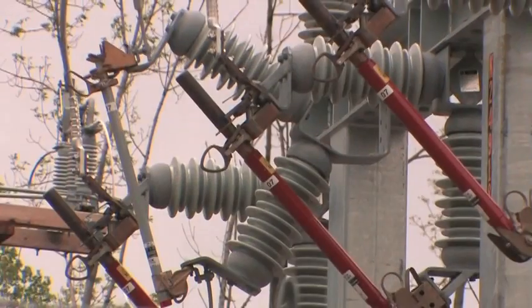The construction and development of the power plant at the Highland Landfill was a fairly challenging undertaking. There's a substation that sits right outside the plant that boosts the voltage from the 4160 generated by the actual three generators up to 34.5, which is the transmission voltage that brings it to the three-ring substation.